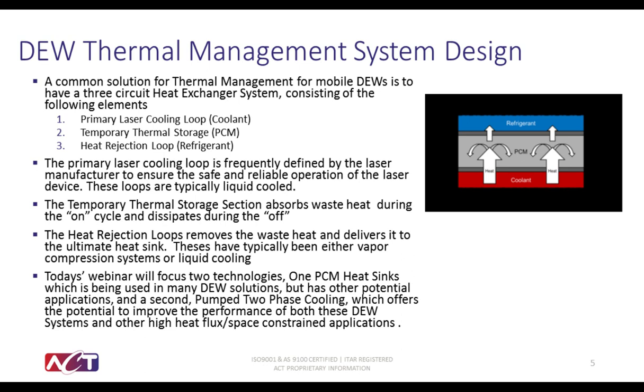An established solution for thermal management of mobile DEWs is a three-circuit heat exchanger system consisting of the following elements: a primary laser cooling loop, seen as red as the coolant; temporary thermal storage, PCM, seen in gray; and a heat rejection loop, seen as blue as the refrigerant. The primary laser cooling loop is frequently defined by the laser manufacturer to ensure safe and reliable operation of the device, and these loops are typically liquid-cooled. The temporary thermal storage section absorbs waste heat during the on cycle and dissipates it during the off cycle. The heat rejection loop removes the waste heat and delivers it to the ultimate heat sink, typically through either vapor compression systems or liquid cooling.